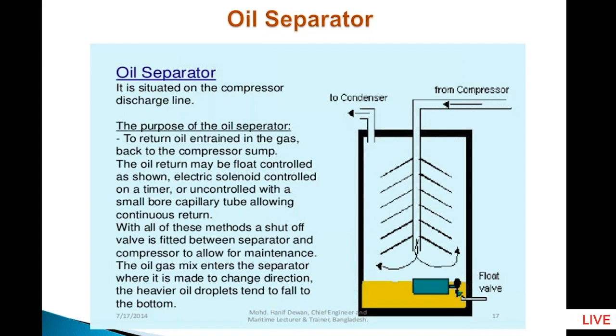This is an oil separator where the oil coming from the compressor through the pipe is distributed into a vessel, and those vessels have pipes. Through those pipes there are small holes, so oil falls down. Oil has a heavier density than ammonia, so oil settles down below, and gas is sucked back. Gas goes to the compressor. The float valve is there, so when the oil level increases, the float valve opens the sump and returns the oil back to the compressor. So this is the function of an oil separator.